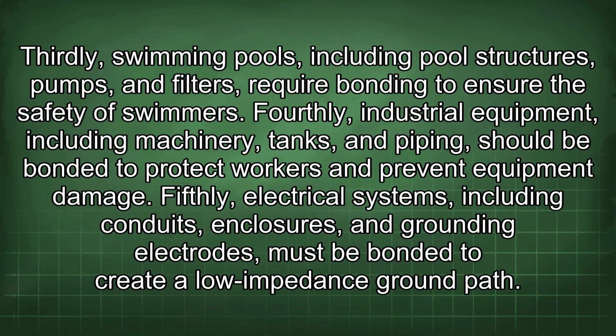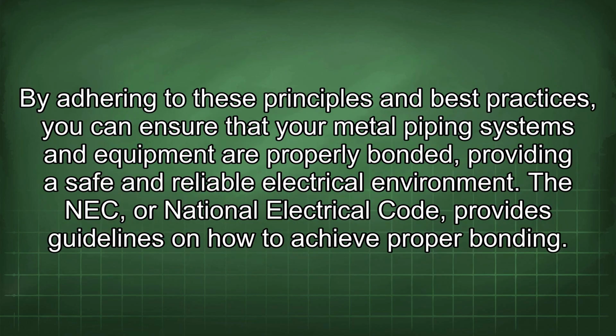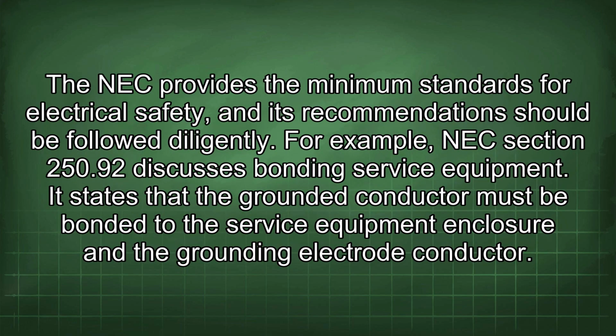Fifthly, electrical systems, including conduits, enclosures, and grounding electrodes, must be bonded to create a low impedance ground path. By adhering to these principles and best practices, you can ensure that your metal piping systems and equipment are properly bonded, providing a safe and reliable electrical environment. The NEC, or National Electrical Code, provides guidelines on how to achieve proper bonding. The NEC provides the minimum standards for electrical safety, and its recommendations should be followed diligently.